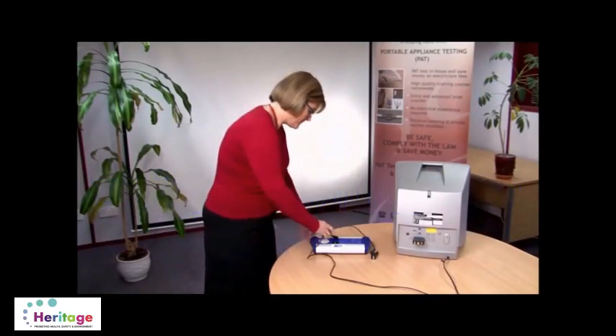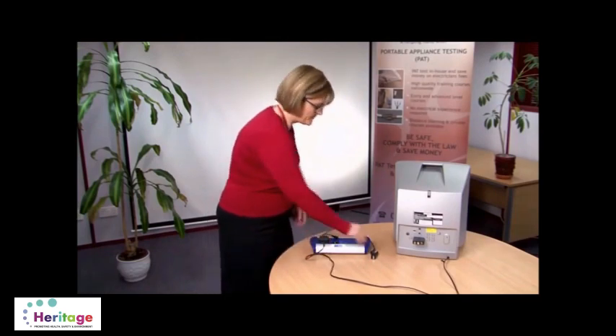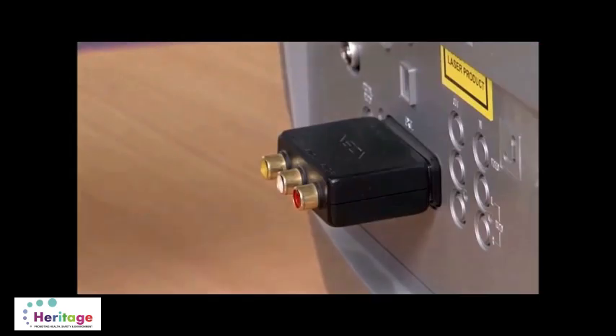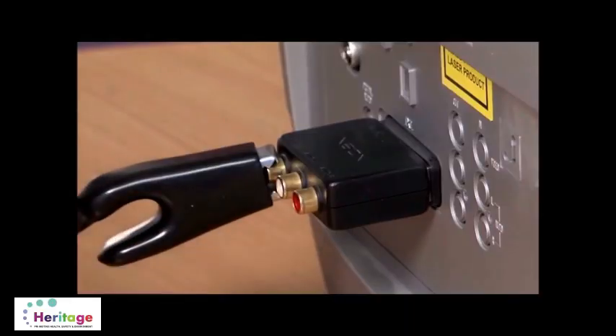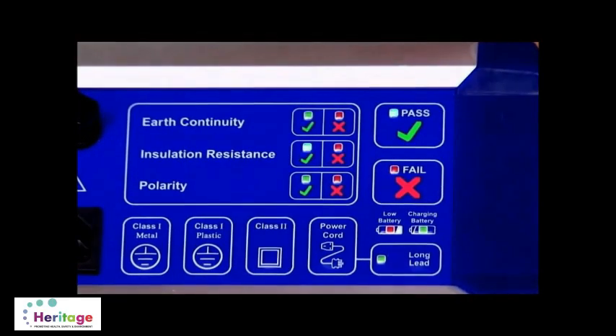Testing a Class 2 appliance. Plug the appliance into the BAT-PAT. If there is any metal work, clip the test lead onto this. Press the Class 2 button and wait for the BAT-PAT to display the results of the insulation resistance test.